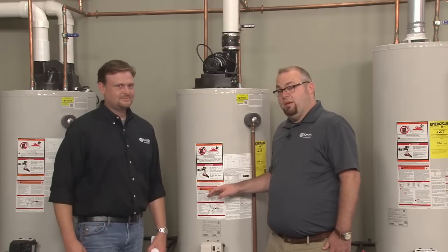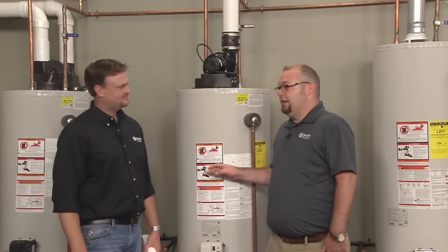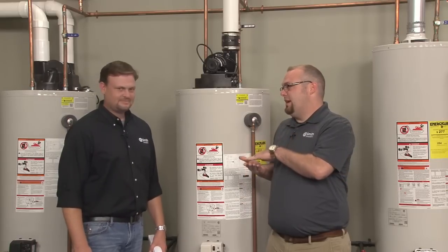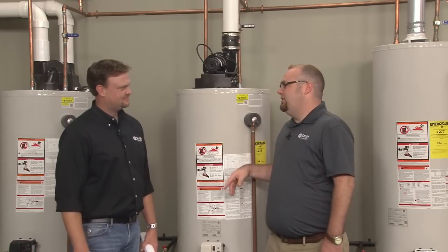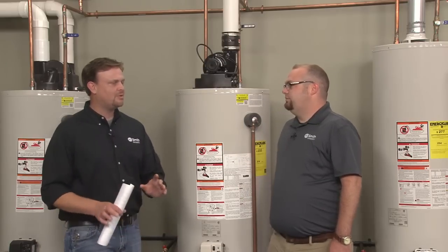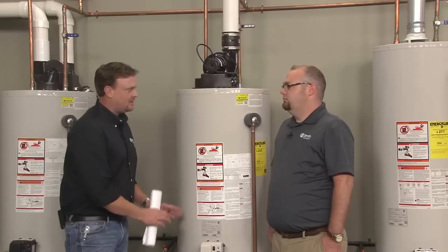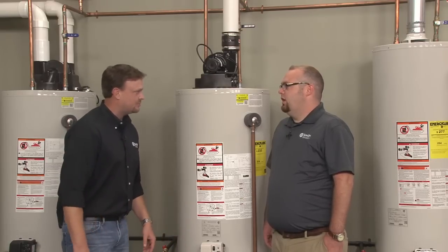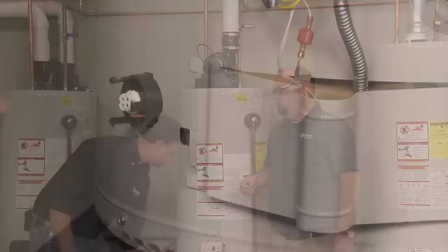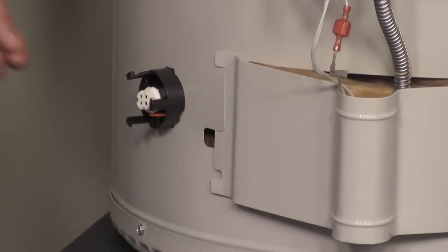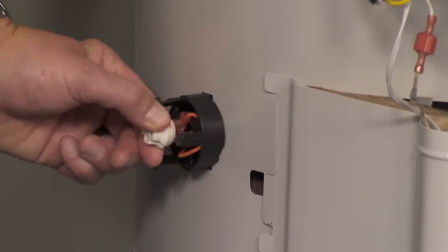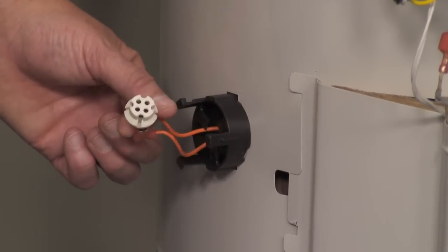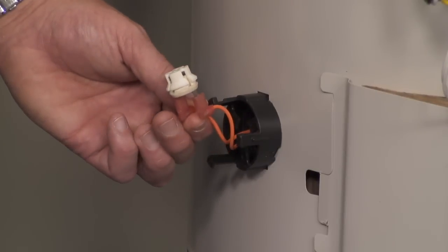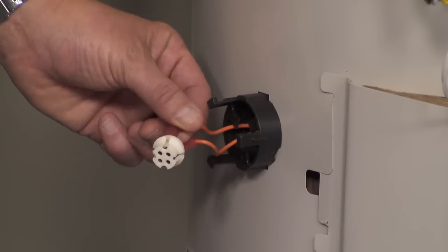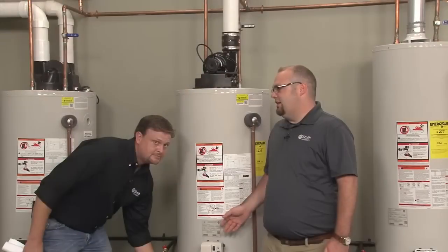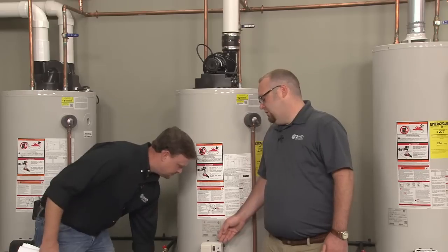If this heater senses flammable vapors, it turns off. If the fumes clear and the resistance of the flammable vapor sensor goes back down within 1 minute, it automatically resets and takes back off running. Let's talk about that real quick. We're sensing flammable vapors, and that has to do with resistance on this sensor, correct? Correct. The sensor is just a resistor. If it picks up something flammable, its resistance increases. Once it goes over a certain point, it pulls a trigger inside the control valve, which locks the heater out. And it's a hard lockout. Resetting the power or unplugging it is not going to fix it. You'll have to do a reset procedure.